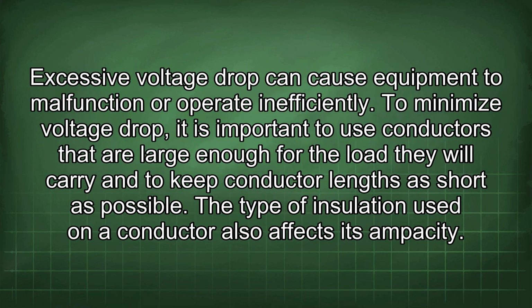Excessive voltage drop can cause equipment to malfunction or operate inefficiently. To minimize voltage drop, it is important to use conductors that are large enough for the load they will carry and to keep conductor lengths as short as possible. The type of insulation used on a conductor also affects its ampacity.